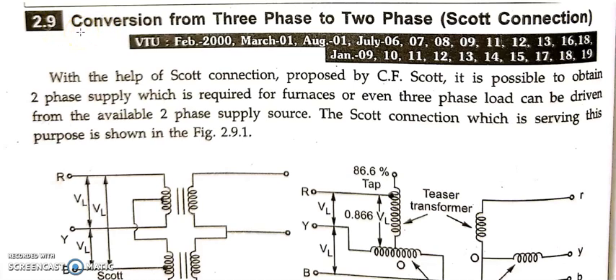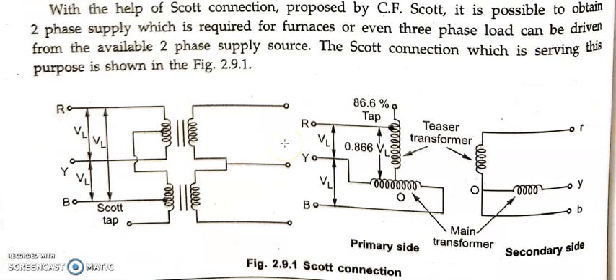Now let us move to the next topic, that is conversion from three phase to two phase connection. That is, we are going to convert the applied three phase into two phase by using the Scott connection, which was initially proposed by C.F. Scott. So what exactly it says is, you should have two single phase transformers, preferably of the same rating. Even if you have transformers of different ratings it is possible, but it is better to have the same rating, with suitable tappings available on the transformer. We have to connect those two transformers in such a manner that the teaser transformer is connected at 86.6% of the tapping, whereas the main transformer is connected with the teaser transformer at 50%.